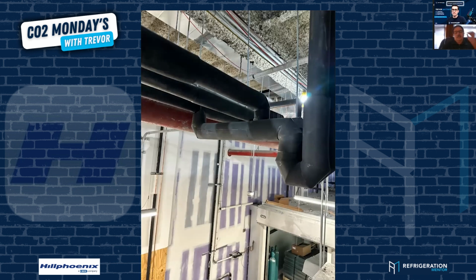All right, so this contractor did a nice job with standard refrigeration piping practices. This is actually the riser to the roof, and you'll notice how he turns. He came off the bullhead for one of his suctions. His other suction comes over and drops down. And I've had contractors literally pipe off the top of the suction line to return back to the rack, and then you're just killing your oil return. And for people out there that don't know, there is a formula for a P-trap. If you don't buy the pre-manufactured P-traps, there's a formula for the pipe size and the depth of the trap. You can find it online almost anywhere.